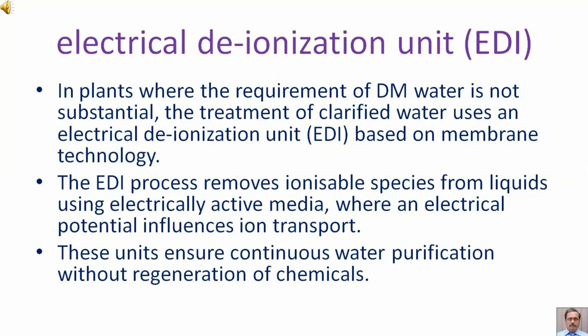The EDI process removes ionizable species from liquids using electrically active media where an electrical potential influences ion transport. These units ensure continuous water purification without regeneration of chemicals.